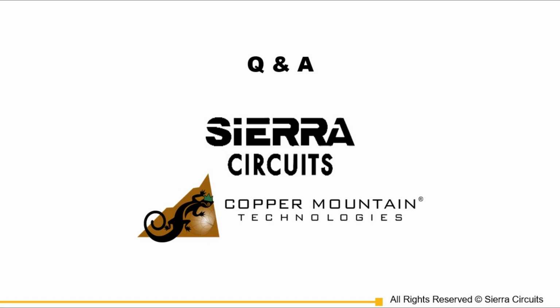That's open, a complex 1J0. And so that has to be filled in for the DC term. If it were short, it'd be -1J0. If it were anything else, you'd have to kind of know what that was and fill that term in. But it's either open or short for the most part. So that has to be filled in as the DC term, and you can enter it or let the VNA figure it out. Yeah, so that's what's happening there.